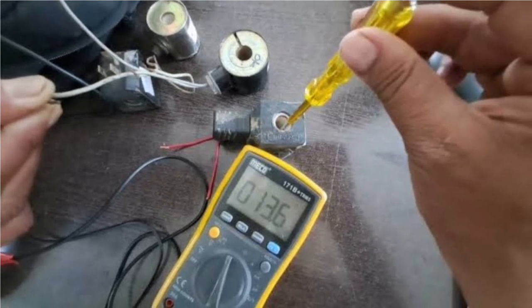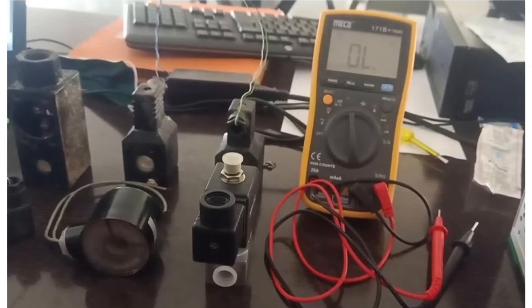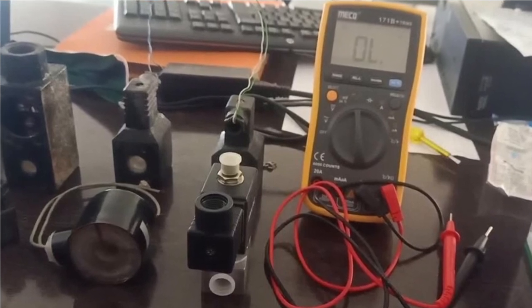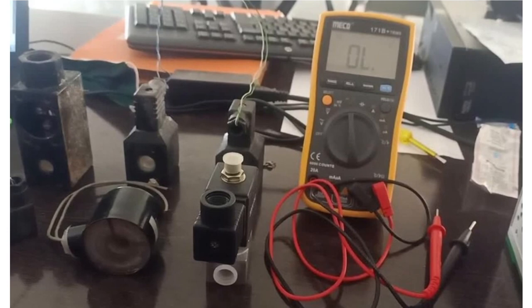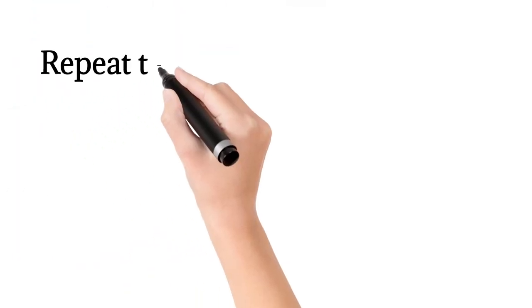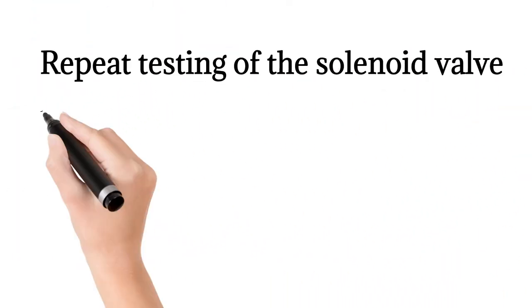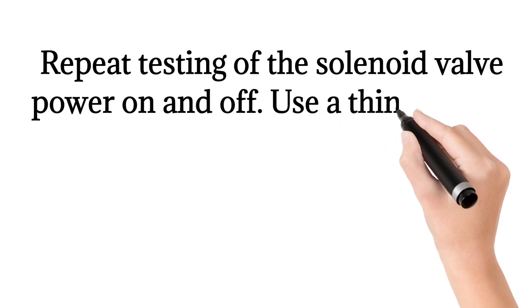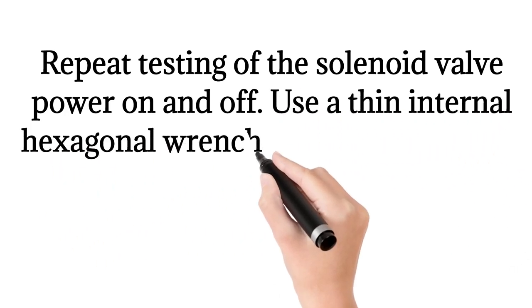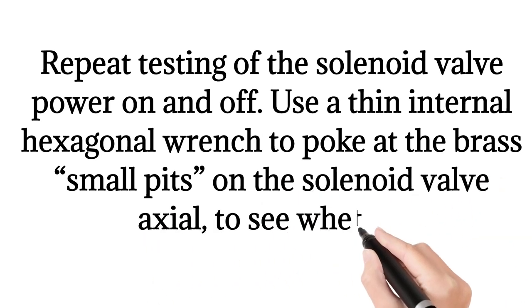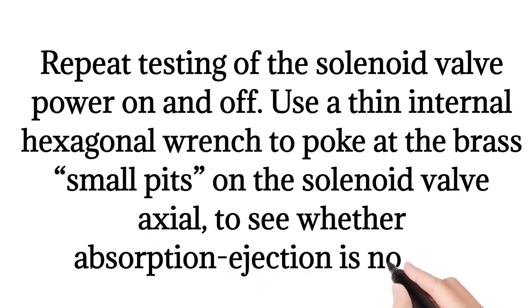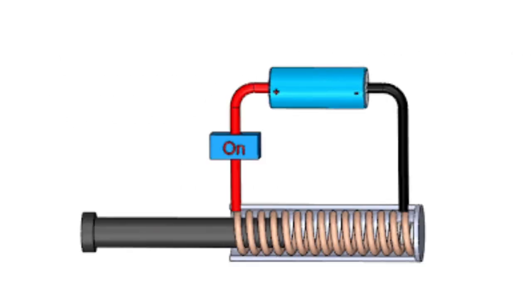Power on the solenoid valve and move the thin steel wire close to the coil to see whether its suction is viable. Repeat testing of the solenoid valve power on and off. Use a thin internal hexagonal wrench to poke at the brass small pits on the solenoid valve axial to see whether absorption and ejection are normal.